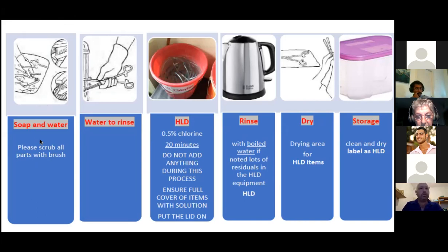When we talk about water, we use either boiled water or distilled water, but boiled water that has been cooled down is more appropriate for the cleaning because it's less expensive. First, we use soap and water to clean the parts. After that, we rinse it with water. And we soak it for 20 minutes in a 0.5% chlorine solution. After the 20 minutes have gone by, we rinse it once more with boiled water that has been cooled down, and we let it dry.